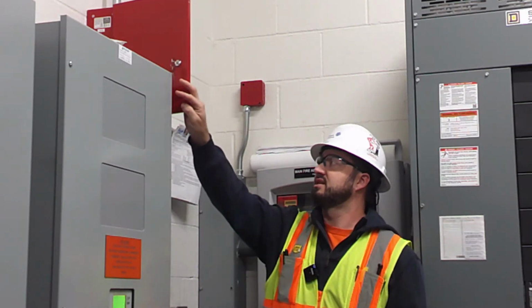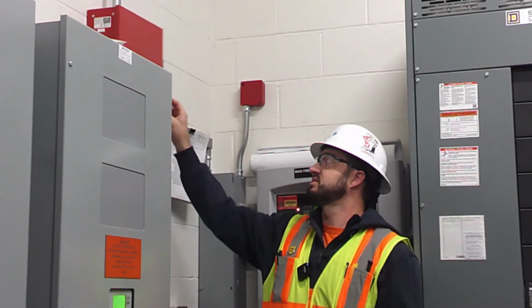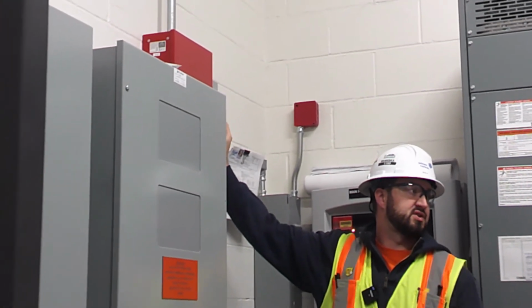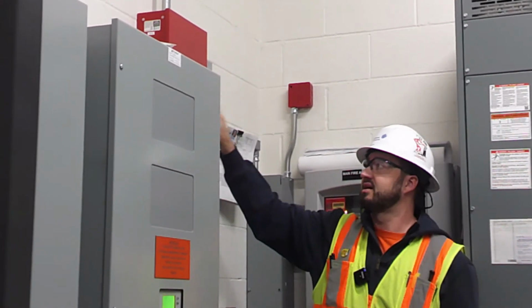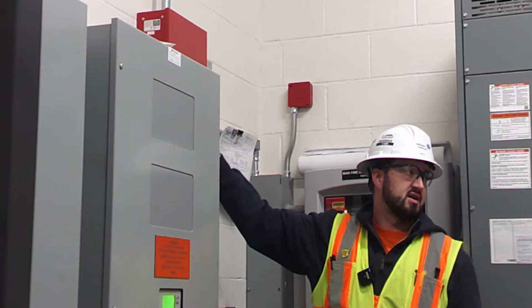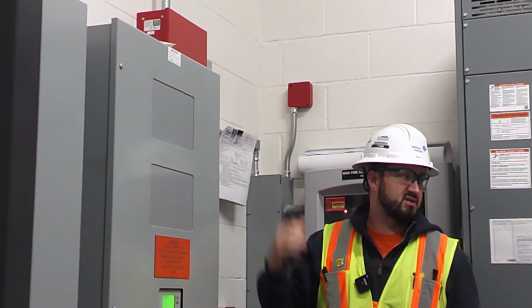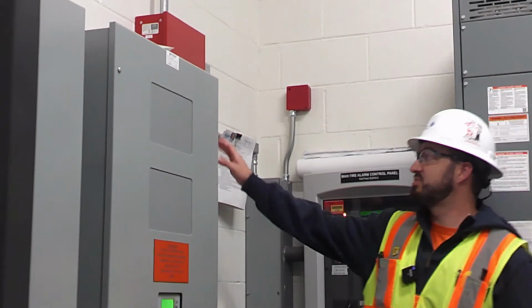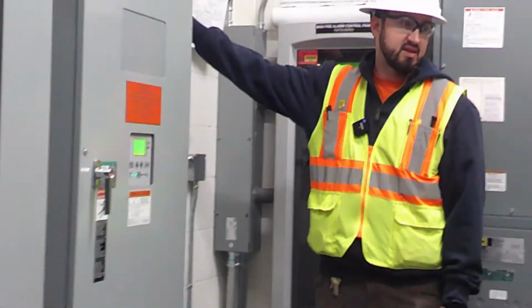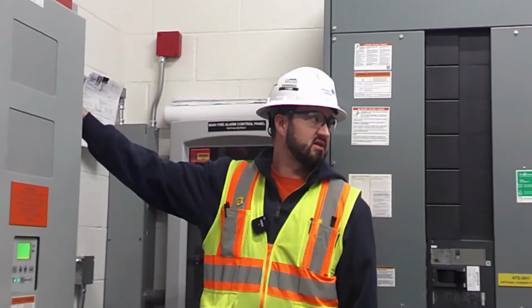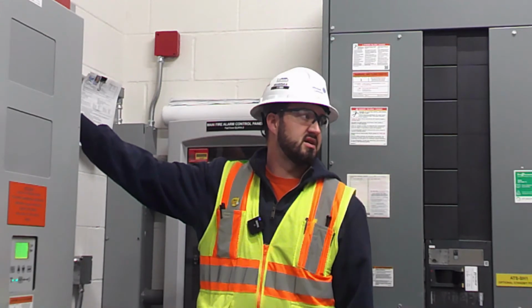But the project did come with an IP dialer, so maybe once you guys take over the school and your server racks are officially up, somebody could come back and generate an IP address for this, and then you'd have an IP dialer and only need 1 phone line as the backup. If you're not going to do IP, it's just another extra piece for an antenna, and then you can change it into a cell dialer. The card is capable of that.